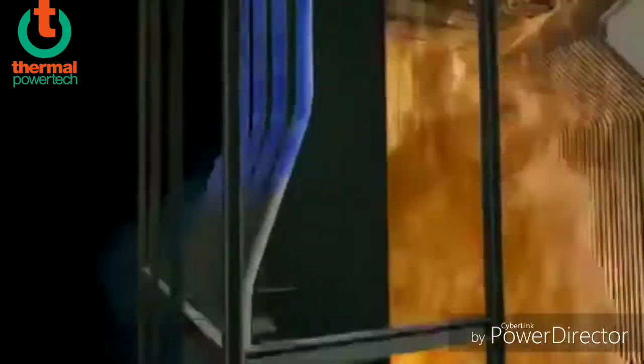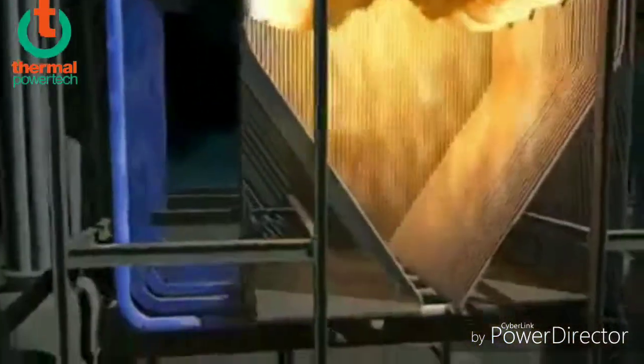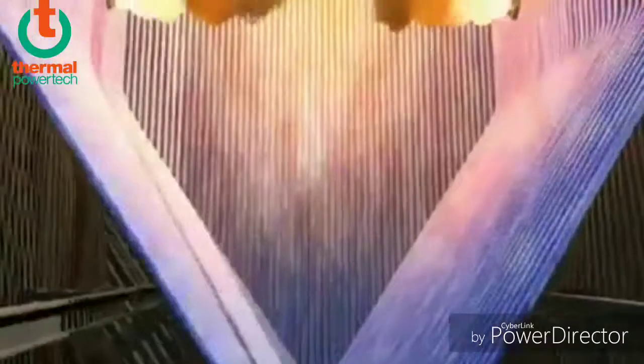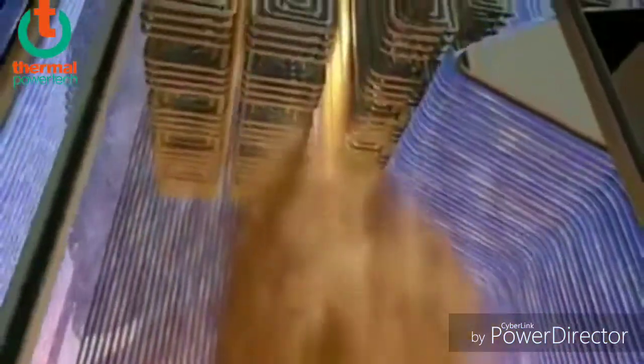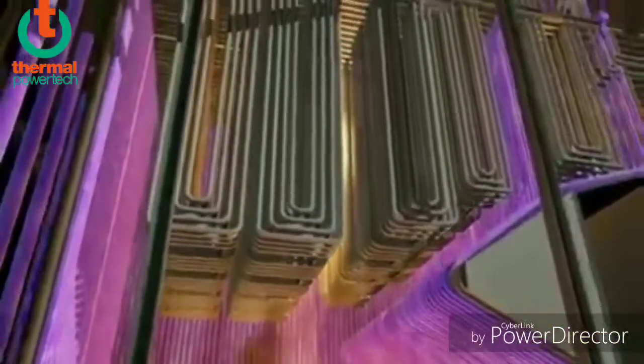Liquid water flows through large downcomers and into the base of the firebox. A network of 2-inch tubes line the firebox walls, and burners force feed a continuous supply of combustible fuel into the ultra-hot firebox. Eventually, the insides of the firebox burn so hot that its surrounding steel walls would melt if not for the tube-lined walls of liquid water.